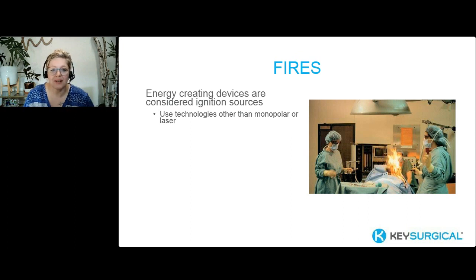So if we can, we should use other technologies than monopolar or laser. As we reflect back on how monopolar devices work, we have a lot longer circuit for it to return. Bipolar instruments, we have the active and return electrode right next to each other, very short distance, a lot more precision, right, and control. Versus monopolar, we have the active electrode, and then somewhere on the body, of course, as close as possible to the surgical site, we have the dispersive electrode. So we have a longer circuit there, and that can lead to a few more complications.